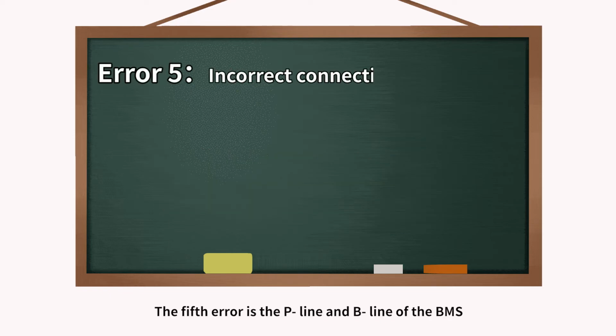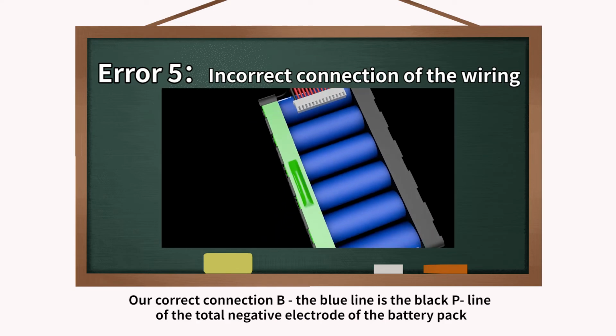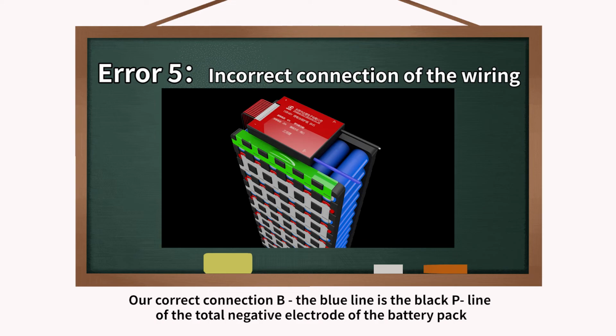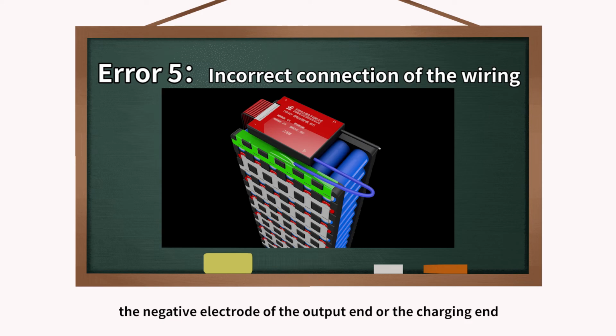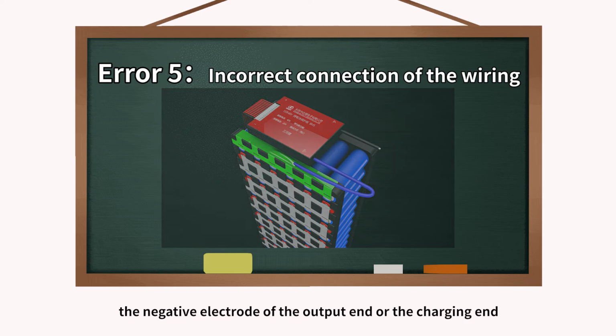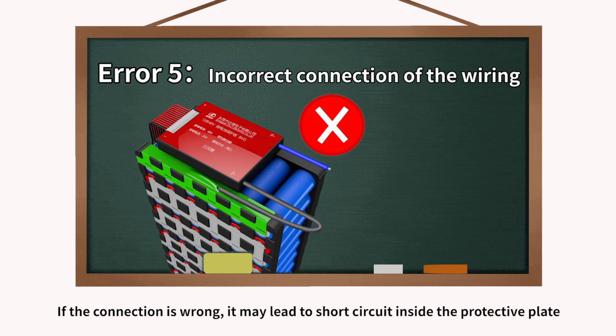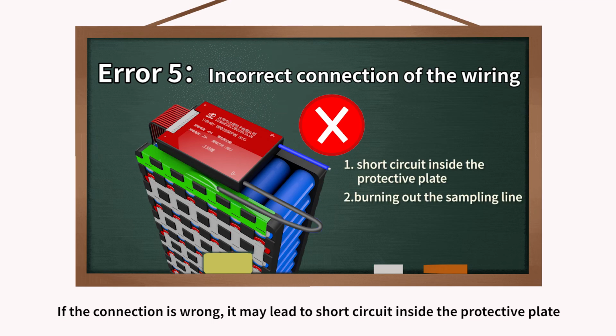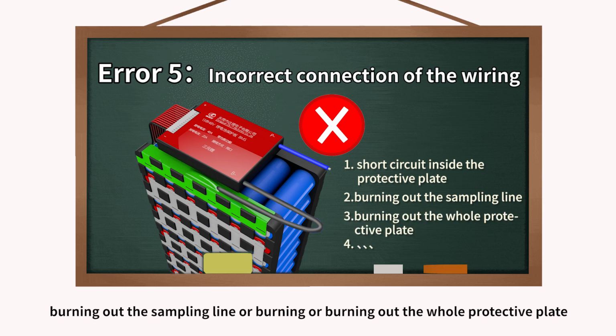The fifth error concerns the P line and B line of the BMS. The correct connection: the blue line is B, the black line is P, the total negative electrode of the battery pack is the negative electrode of the output end or charging end. If the connection is wrong, it may lead to a short circuit inside the protective plate, burning out the sampling line or burning out the whole protective plate.